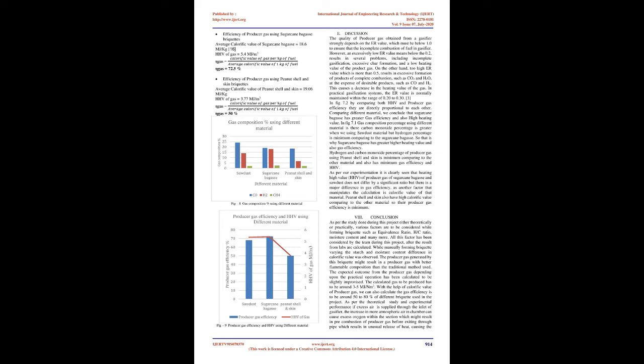The volume percent of CO, CO2, H2, H2O, CH4, C2 and higher hydrocarbons, and N2 are measured to calculate the gas energy content or to analyze gasifier operation. Gas energy content can be calculated from gas composition or measured calorimetrically without the need to know composition. The gas must have an energy content greater than 4 MJ/Nm³ for most applications. As per the testing result from the lab defining the ultimate analysis of our briquette material, further results would be obtained. The average composition of the gas produced on dry basis is in the following range of volume percentage: N2 equals 45-60%, CH4 equals 0.25-2.5%, H2 equals 10-22%, CO equals 13-25%, CO2 equals 8-19%, and traces of C2H2 and C2H4.